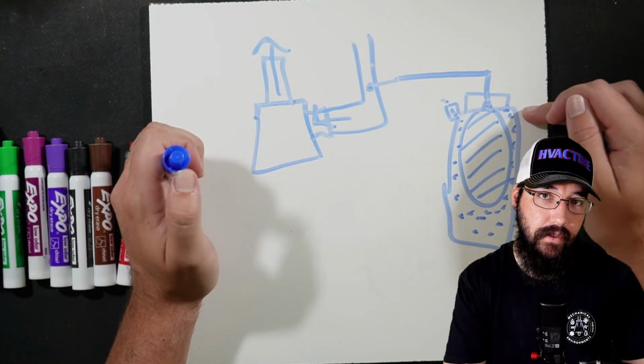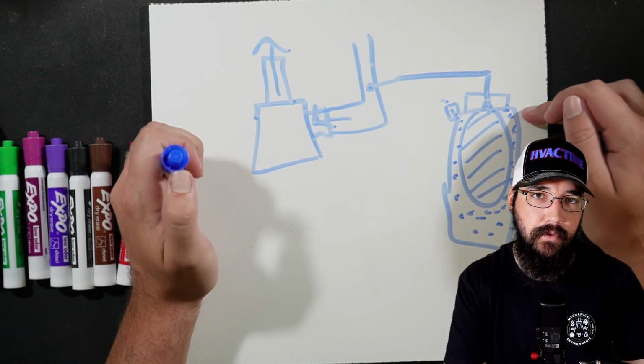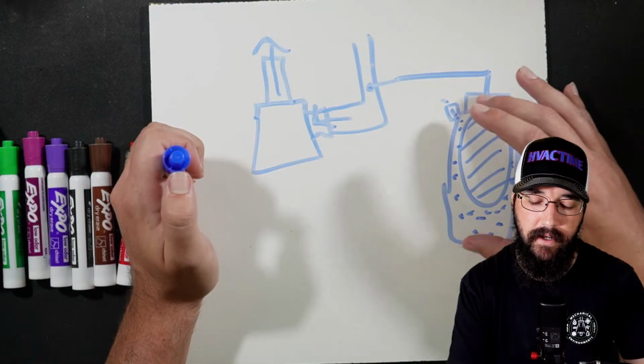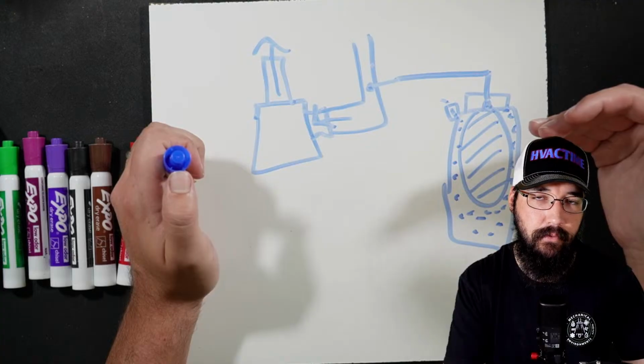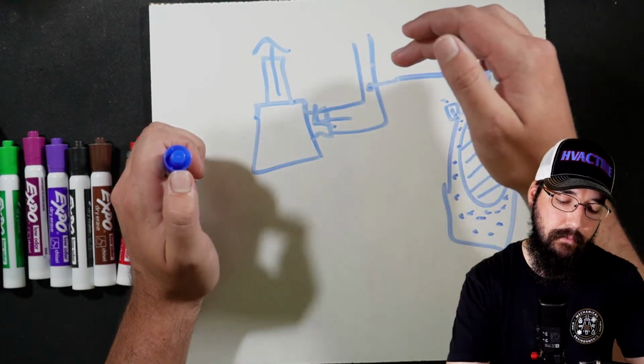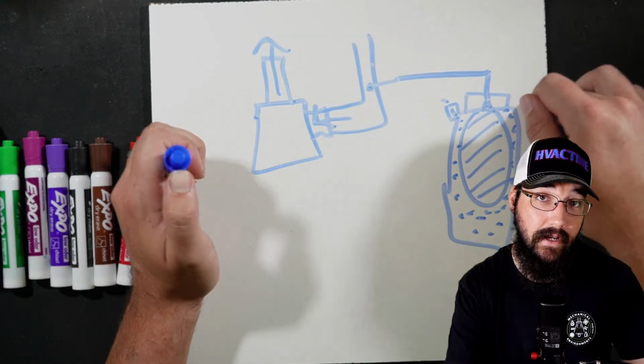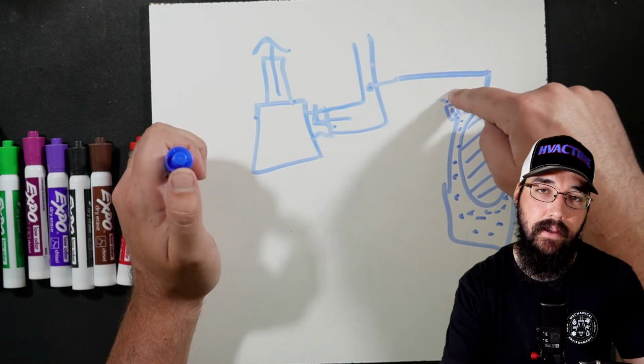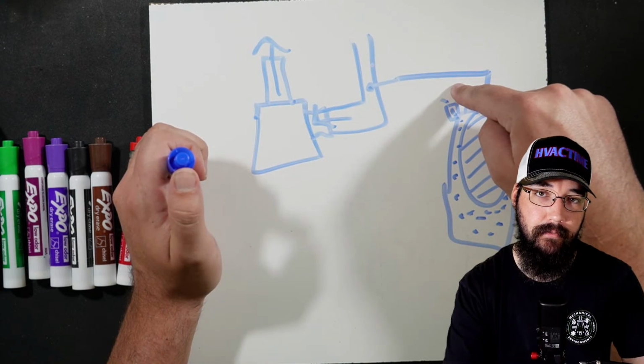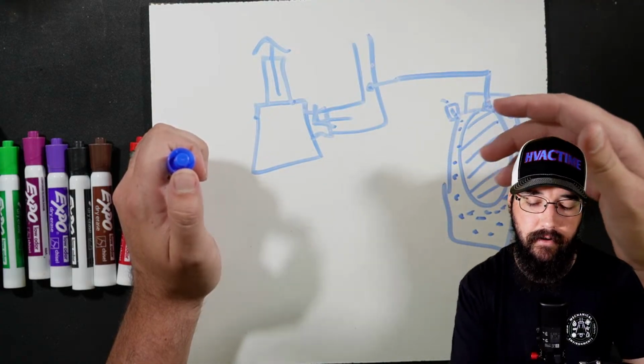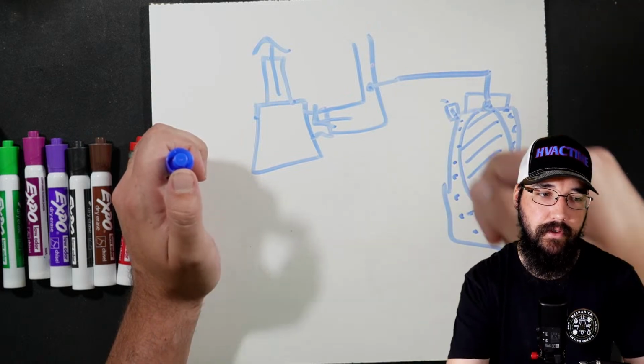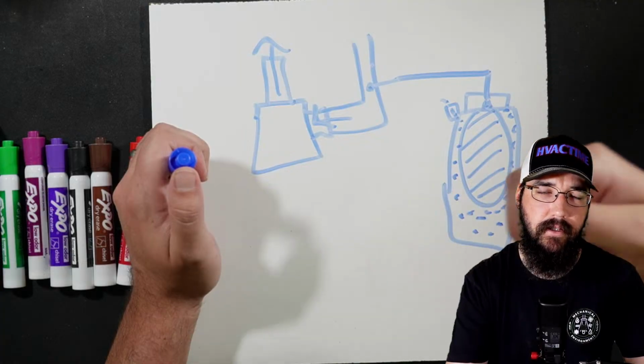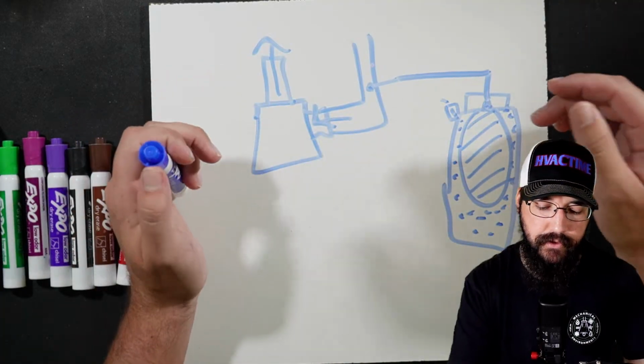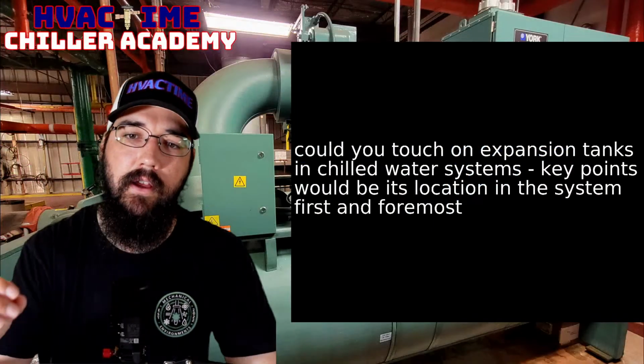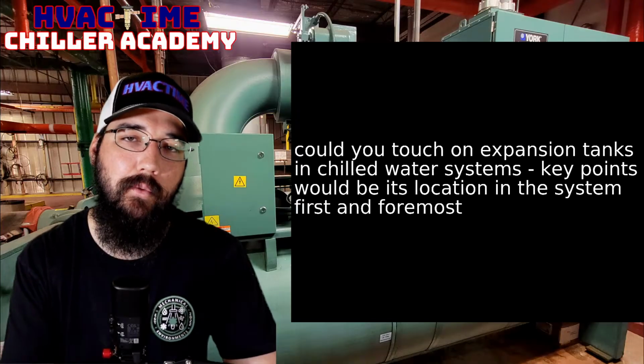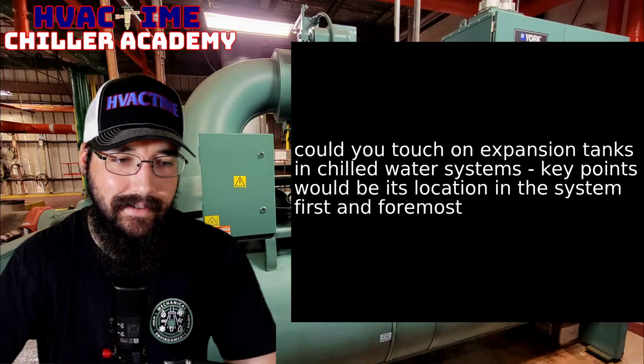So if this is set to the factory default of 12 psi, well, this has no purpose in the loop. It's serving absolutely no purpose because it doesn't have enough counter pressure to actually act against that bladder at that point, which completely nullifies its effect. So it's important that we know where it's at in location, what the loop pressure is expected to be, and that this tank pressure is calibrated to that pressure. And to my understanding, there's no issue just putting standard air in here. I know some guys put nitrogen in there, with their regular gauge hose. So you can go about that process however you wish. But that is the core concept of what an expansion tank is and where it would be, and then how you would go about calibrating that in the system.